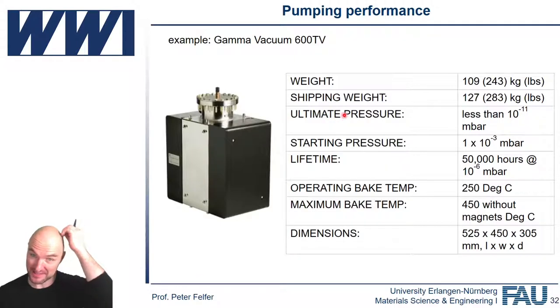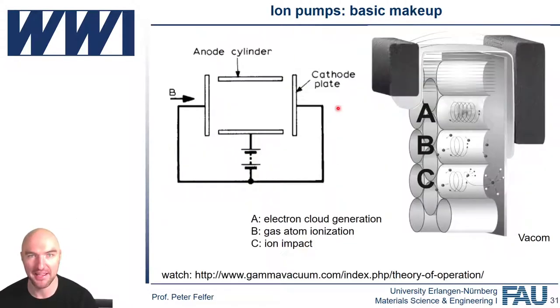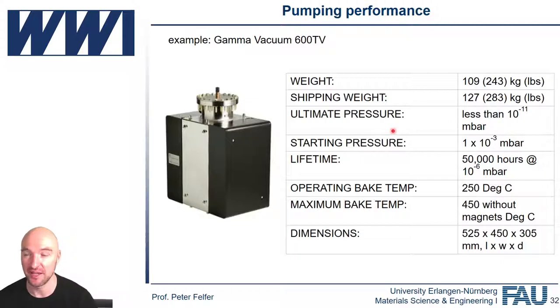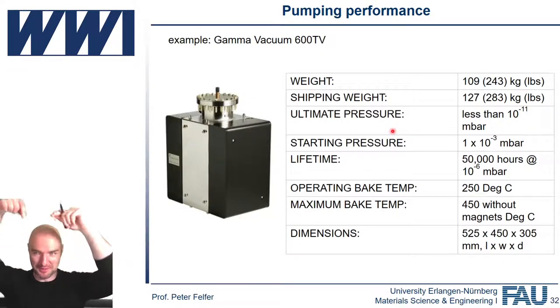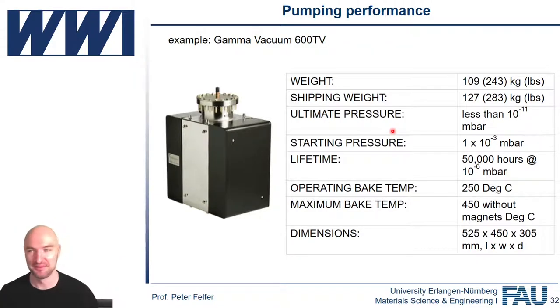They have some downsides as well. The problem is you need big magnets in order for the ionization to work well. So they're pretty heavy. So your only chance to mount them is below your system, which isn't usually great, especially if you want to go onto an optical table or something like that.